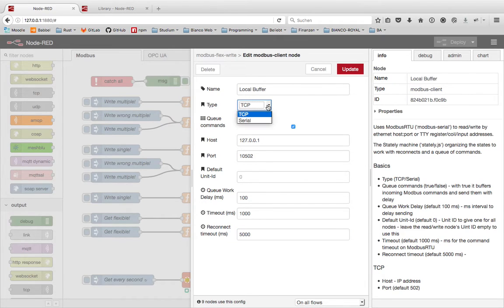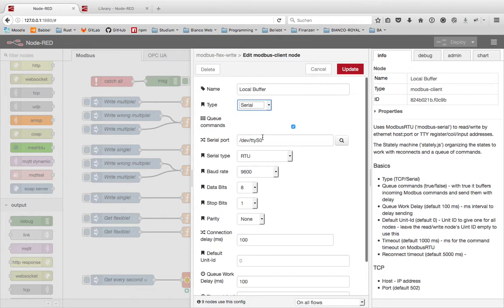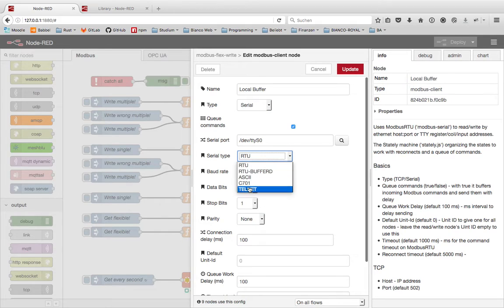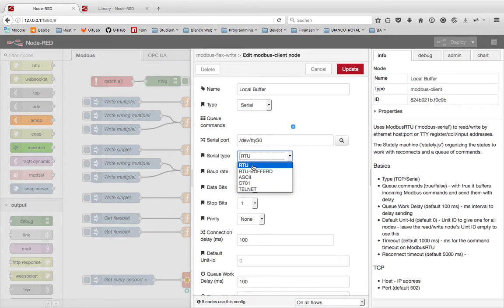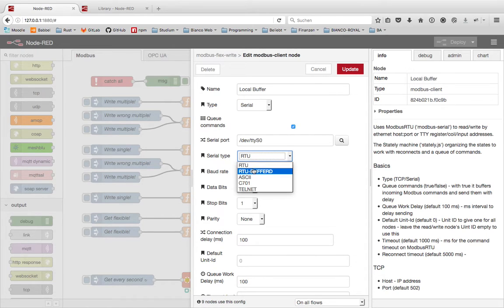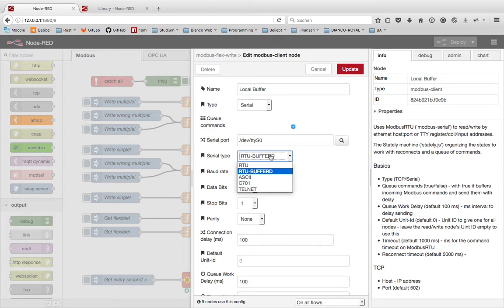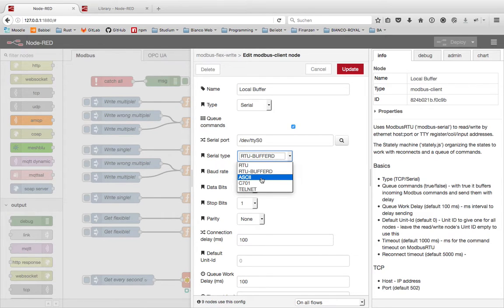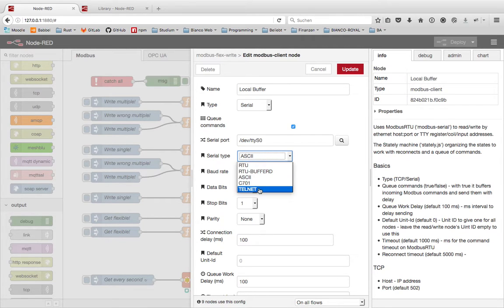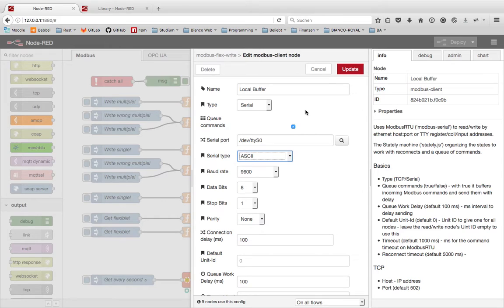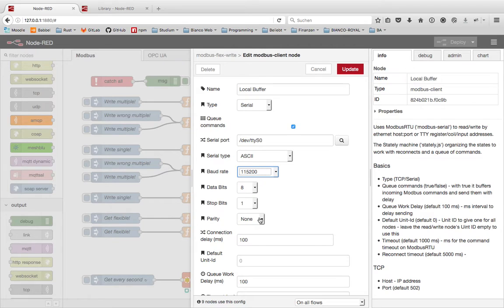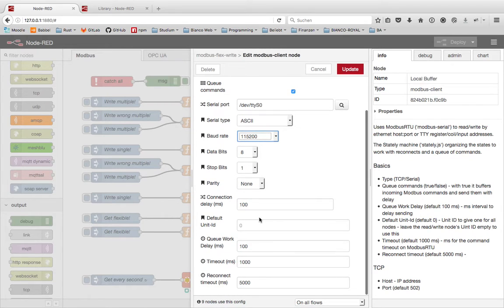When we go to serial we have a new selection of more serial types. RTU is sending directly and you have to get your responding at once. RTU buffered means that all the data will be buffered until the responding is completed. Then ASCII and all this stuff is a whole new way to communicate with Modbus devices. You can also setup the speed.